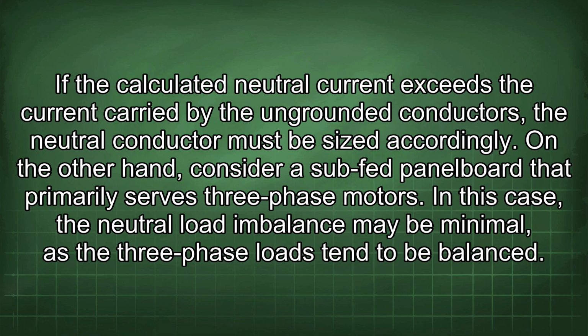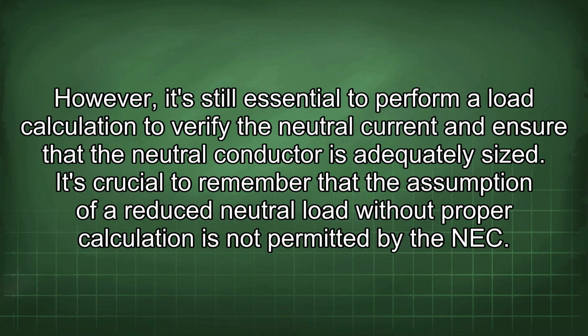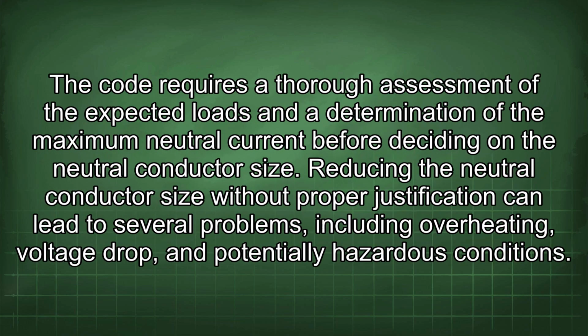On the other hand, consider a sub-fed panel board that primarily serves three-phase motors. In this case, the neutral load imbalance may be minimal, as the three-phase loads tend to be balanced. However, it's still essential to perform a load calculation to verify the neutral current and ensure that the neutral conductor is adequately sized. It's crucial to remember that the assumption of a reduced neutral load without proper calculation is not permitted by the NEC. The code requires a thorough assessment of the expected loads and a determination of the maximum neutral current before deciding on the neutral conductor size.